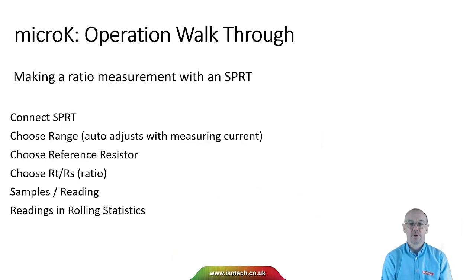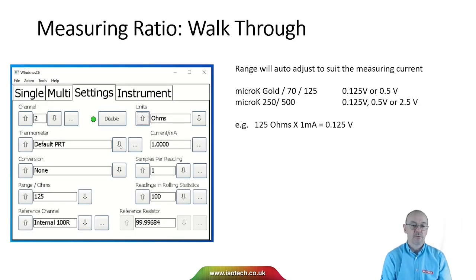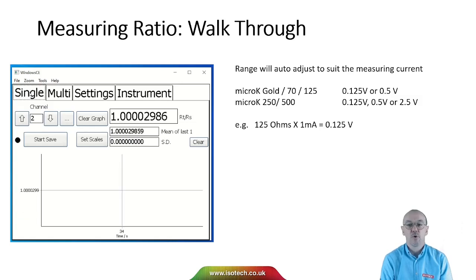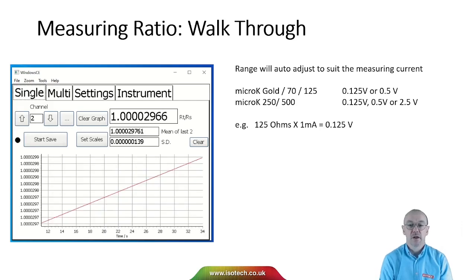Let's walk through how to make a ratio measurement with an SPRT. Very simply: connect the SPRT, choose the range, choose the reference resistor, set ratio, and we have optional values for statistics. For example, with a default PRT at a 125 ohm range at 1 milliamp using the internal 100 ohm reference resistor, we select RT over RS for units and we're good to go. The micro-K Gold 70/125 has 125 mV and 500 mV ranges; micro-K 250/500 also has a 2.5 V range, and the micro-K automatically sets the range appropriately.